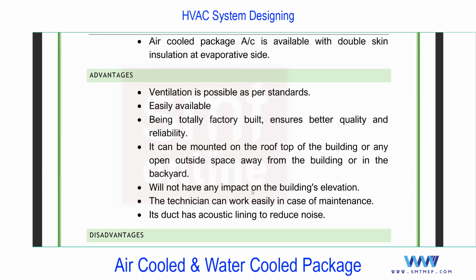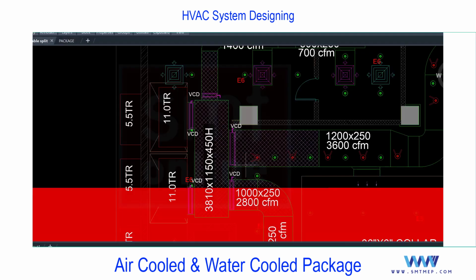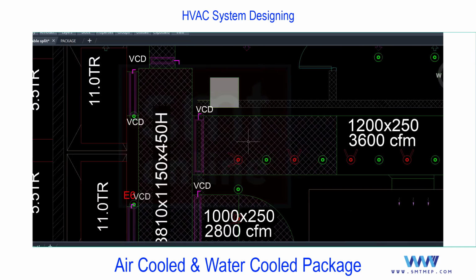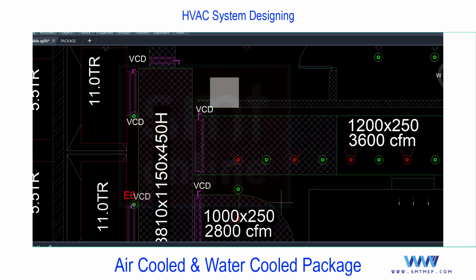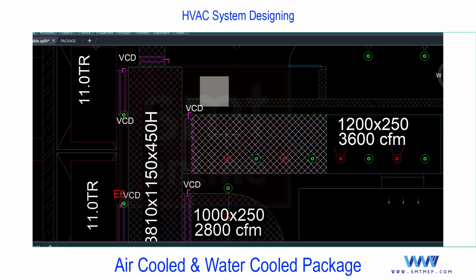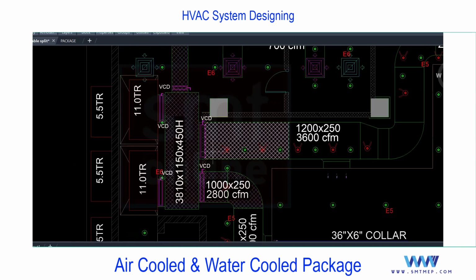Acoustic lining means inside the duct. You see this hatching, double hatch, represents lining, acoustic lining. It can be nitrile rubber or it can be fiberglass. We have a separate topic of duct insulation. Under that you'll find thermal insulation and acoustic lining, and you see double hatching represents internal lining which is used to reduce the noise. Not only for package, even for other systems, for duct we require this insulation to reduce the noise. That is called acoustic lining.